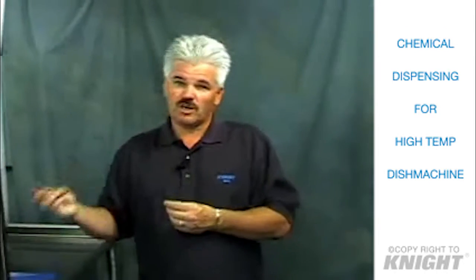Or, if I want to make it run a little longer, what I can do is change it to recharge every 2 racks. So I could change that time and let it run a little longer every 2 racks instead of every rack. So that's a simple way to understand how you can make a probeless system work and be just as accurate and give you everything that you need to get the settings and the desired economical needs of your customer.